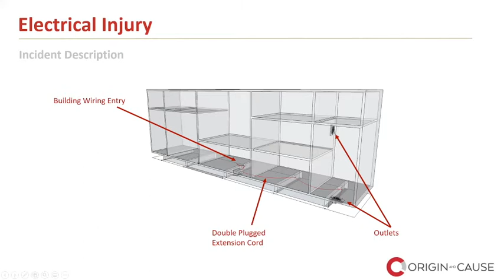The main issues were with supported cables. Power cables need to be supported, stapled to a joist or stud every so many centimeters, that sort of thing. The next was the fact that the junction box underneath the cabinet was concealed and not visible for maintenance. The third was the improper use of a flexible cord, a flexible cord being the term the code uses for basically extension cords. So the next question was, did these code violations constitute a hazard?